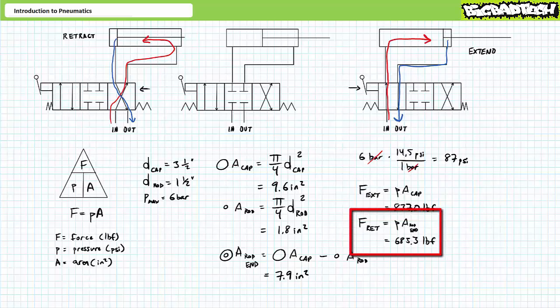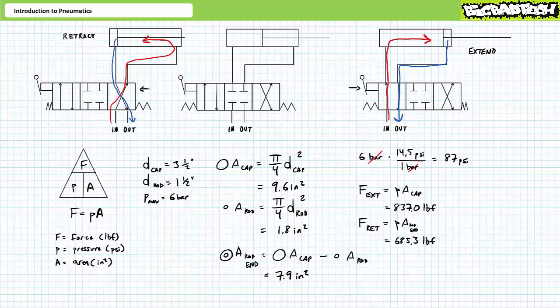Retraction necessitates pressurized fluid enter the rod end port and the cap end port be exhausted at low pressure. During retraction, pressurized fluid acts on the ring-like annular surface area within the rod end. The area of the rod is equal to pi over four times the diameter of the rod squared. Substituting in our given values results in a rod area of roughly 1.8 square inches. The ring-like rod end area is equal to the area of the cap minus the area of the rod, resulting in a rod end area of roughly 7.9 square inches. An application of Pascal's law demonstrates 87 psi acting on a surface area of 7.9 square inches results in a maximum retraction force of roughly 683.3 pounds force.